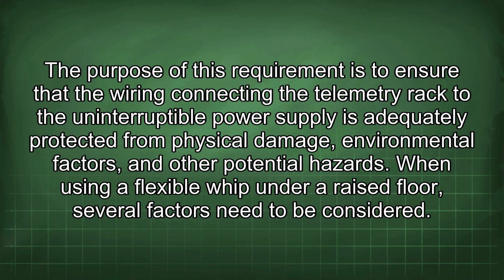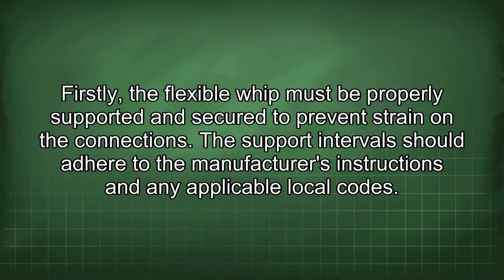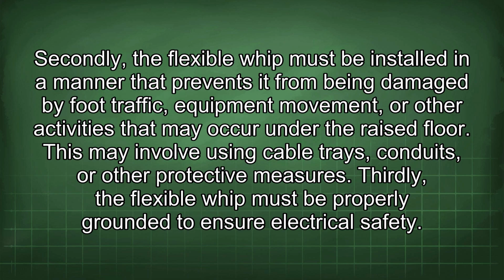When using a flexible whip under a raised floor, several factors need to be considered. Firstly, the flexible whip must be properly supported and secured to prevent strain on the connections. The support interval should adhere to the manufacturer's instructions and any applicable local codes. Secondly, the flexible whip must be installed in a manner that prevents it from being damaged by foot traffic, equipment movement, or other activities that may occur under the raised floor. This may involve using cable trays, conduits, or other protective measures.